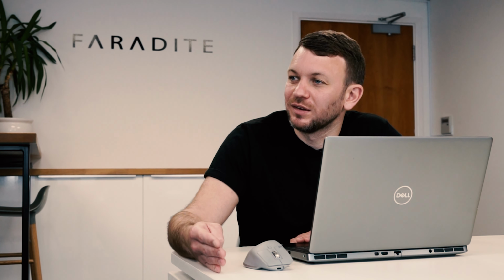This might be a commercial property where you might have a facilities manager who wants to dynamically change that timeout to avoid the lights turning off, or maybe the room has changed use. And that needs to be upgraded or changed, and they don't necessarily want to get the KNX integrator to come back in and change it in ETS. Instead, we need to give the ability to change the timeout from an external device, which means enabling a group object to do that. So let's have a look inside ETS at how you achieve that.